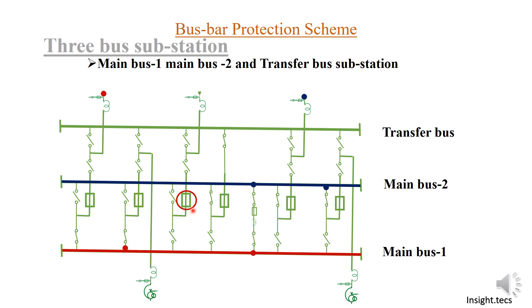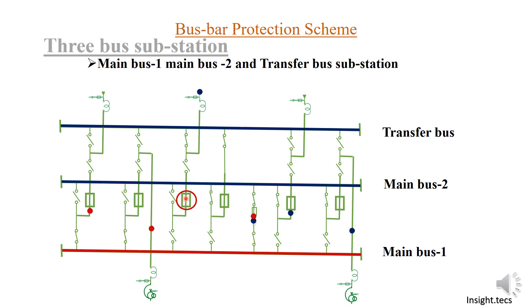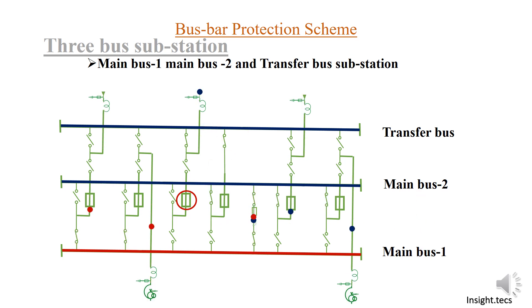We also close the feeder isolator for connecting to the transfer bus. Now power flow occurs through this feeder, through the transfer bus breaker, and your bus will be charged. The benefit of the transfer bus is clear — even if the main feeder providing power supply to the bus is under maintenance or outage, power evacuation through this feeder will continue with no interruption. This is how the transfer bus arrangement is used along with Main Bus 1 and Main Bus 2.